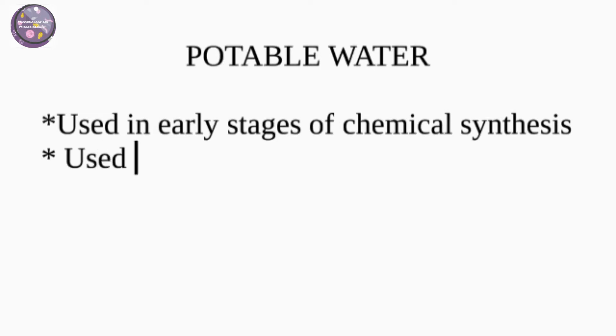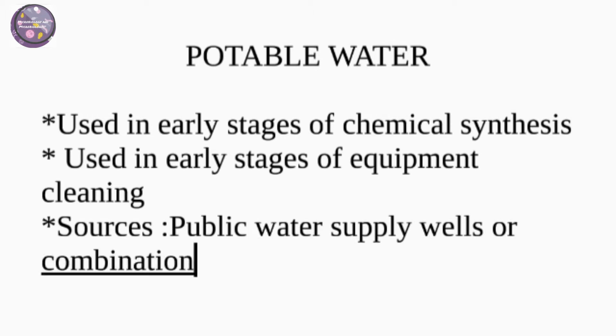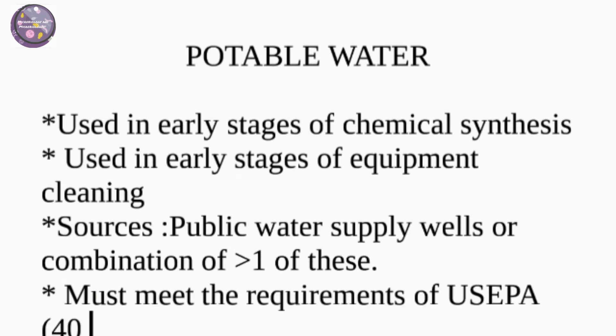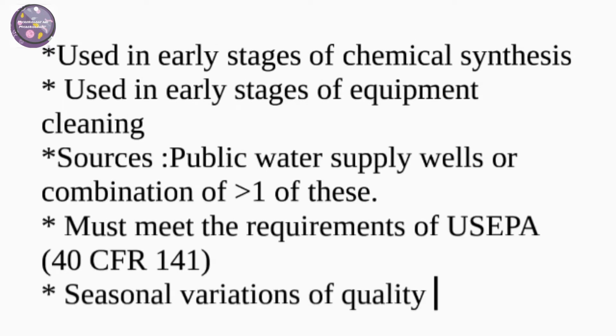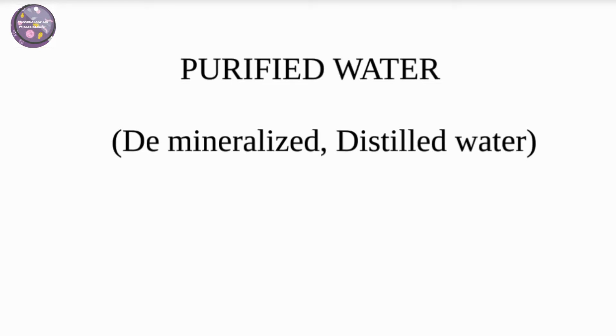Potable water is used in the early stages of chemical synthesis and in early stages of equipment cleaning. Its sources may be public water supply, wells, or a combination of more than one of these. It must meet the requirements of US EPA 40 CFR 141. Seasonal variations in quality may occur and must be considered for treatment before usage.